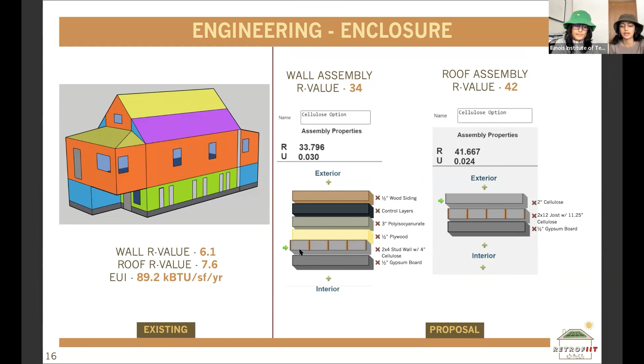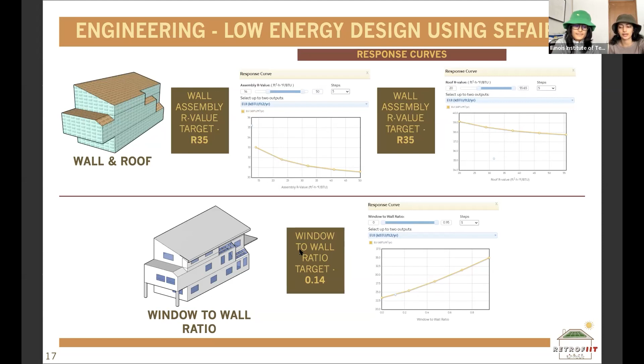Because our building is intended to be deeply affordable, we wanted to be selective with where we spent money. These curves helped us determine which aspects of the building have the biggest effect on EUI and when we would see diminishing returns. Based on the curves produced, we had a target R value of 35 for the wall assembly and 40 for the roof assembly. We also found that our EUI was highly responsive to the window to wall ratio, and we decided to target a ratio of 0.14 to ensure that the daylight requirements were met.